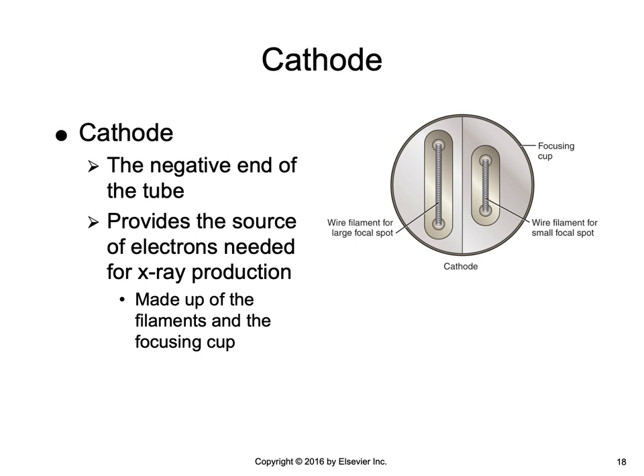The cathode is the negative end of the tube and it provides the source of electrons needed for x-ray production. The cathode is made up of the filaments and the focusing cup, and is connected to two different parts of the x-ray circuit: the filaments are connected to the filament circuit, and the focusing cup is connected to the secondary circuit. Shown here is a front view of the cathode focusing cup with two filaments situated within it — the large focal spot filament on the left is noticeably bigger than the small focal spot filament on the right.